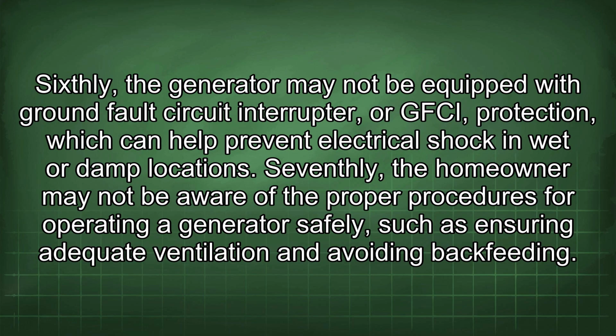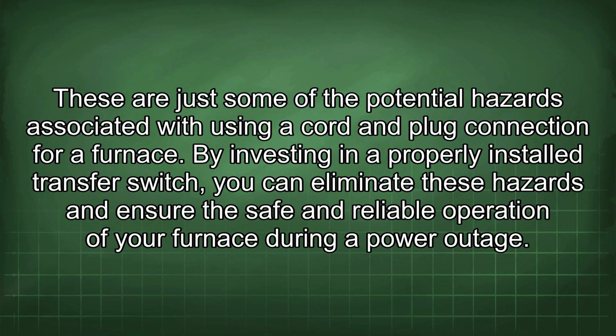Seventhly, the homeowner may not be aware of the proper procedures for operating a generator safely, such as ensuring adequate ventilation and avoiding backfeeding. These are just some of the potential hazards associated with using a cord and plug connection for a furnace. By investing in a properly installed transfer switch, you can eliminate these hazards and ensure the safe and reliable operation of your furnace during a power outage.